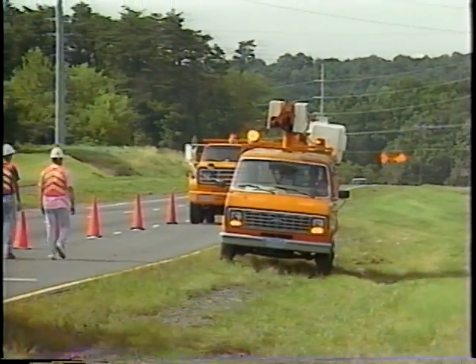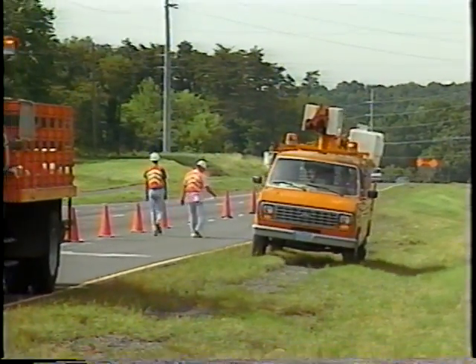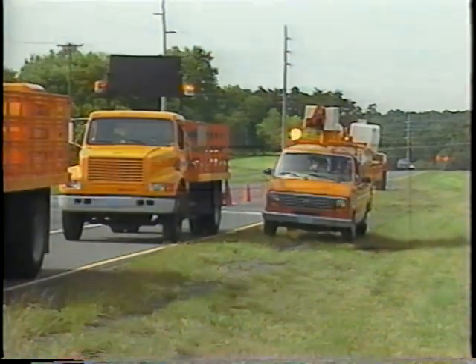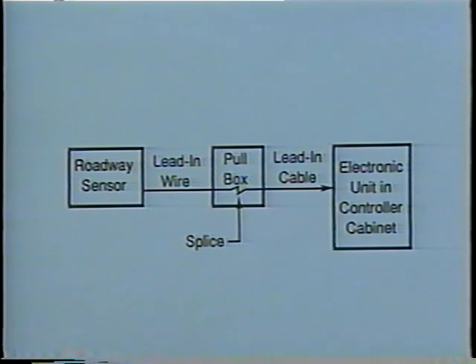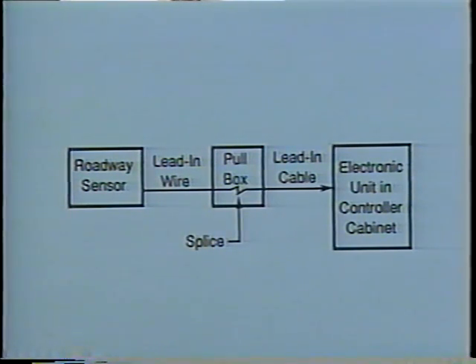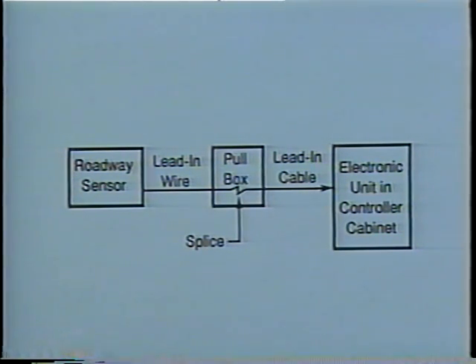This completes the pre-installation process. The loop detector system is composed of one or more wire loops embedded in the pavement to act as a sensor, a splice between the lead-in wire and the lead-in cable in the pull box, the lead-in cable—usually in a conduit—running to the terminal strip in the controller cabinet, a cable from the terminal strip to the electronic detector unit, and finally the electronic detector unit itself.